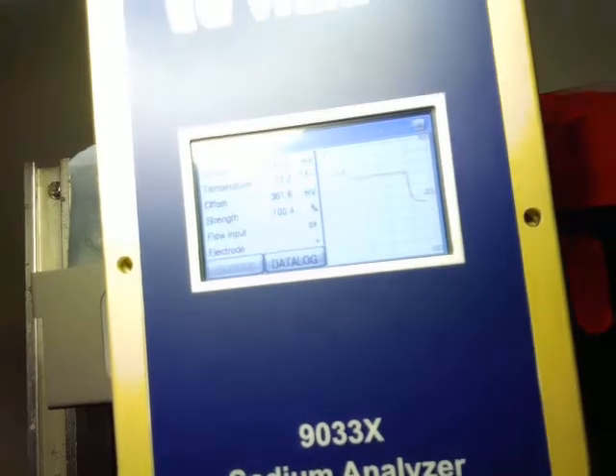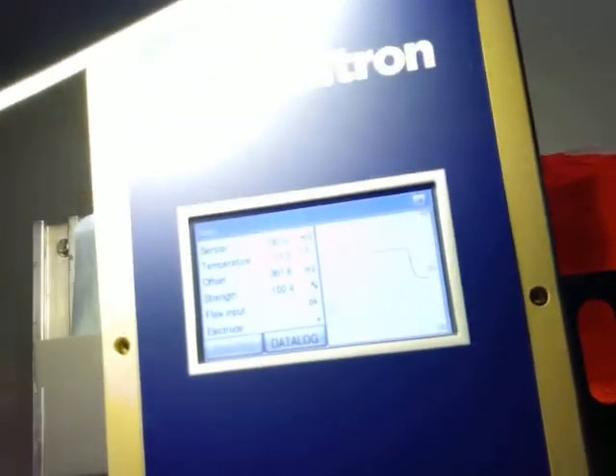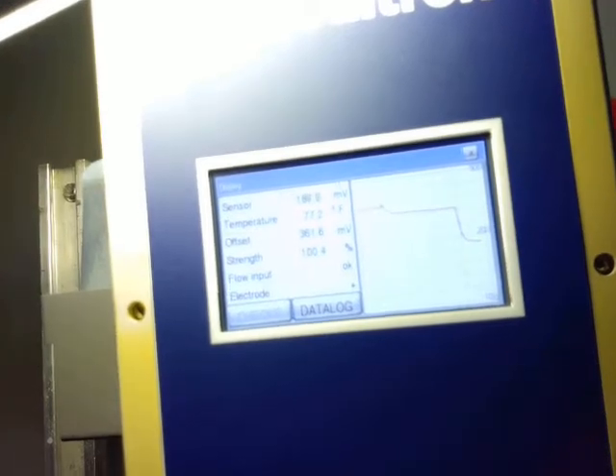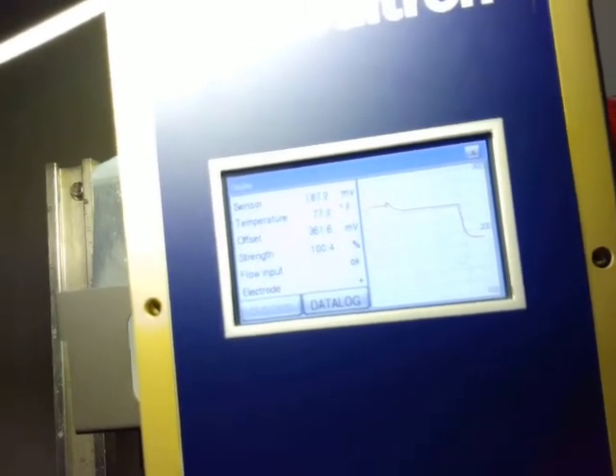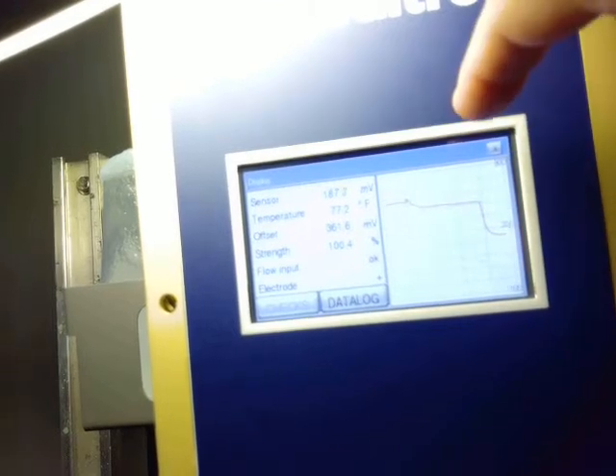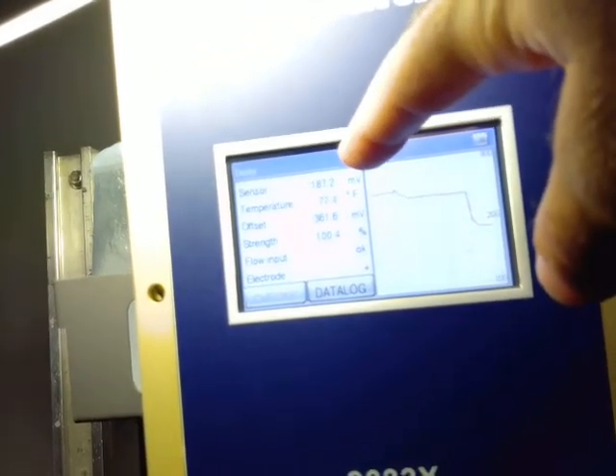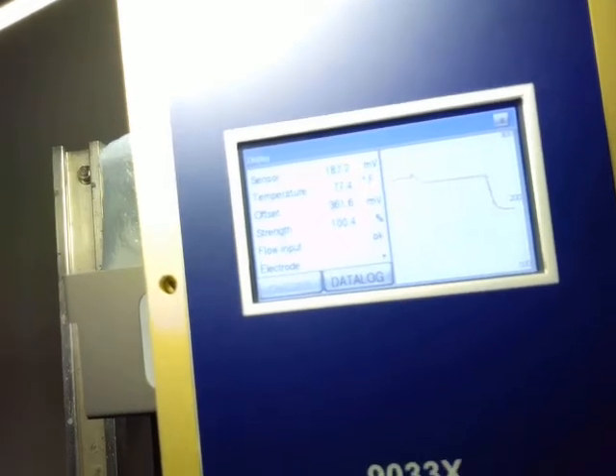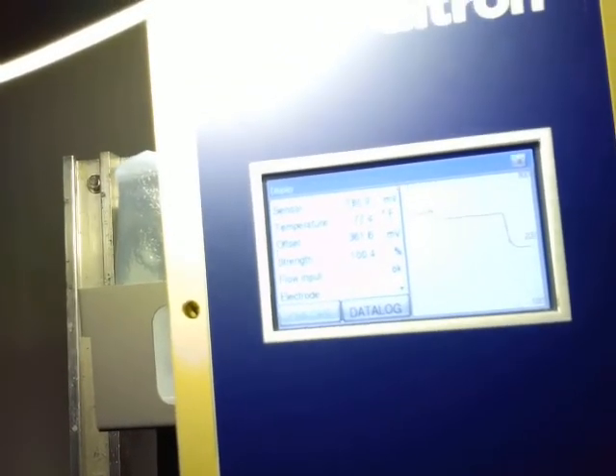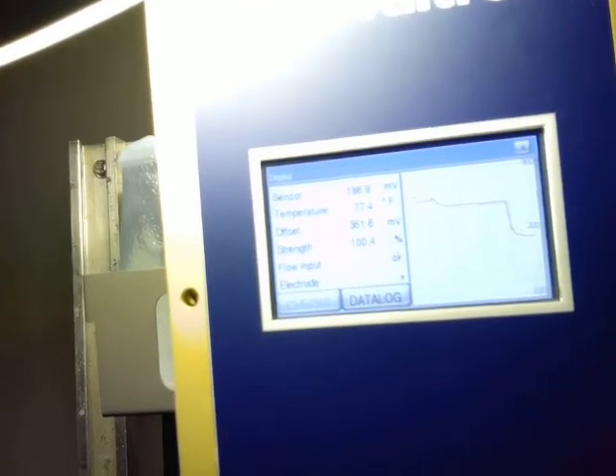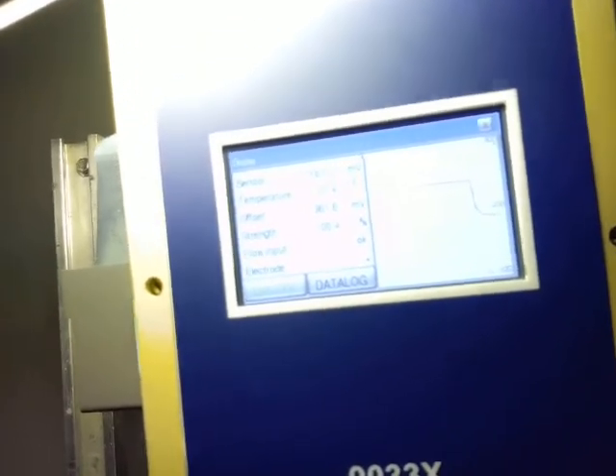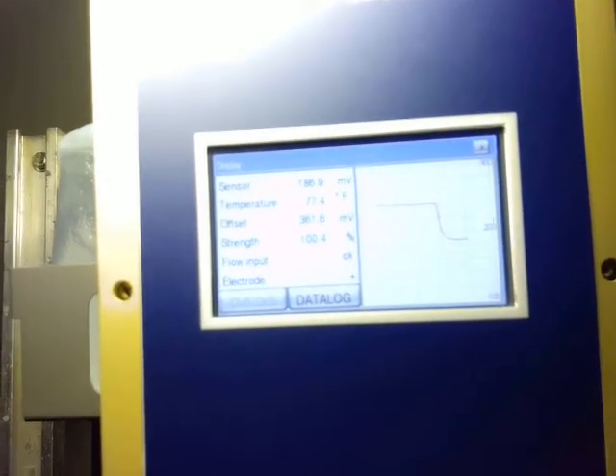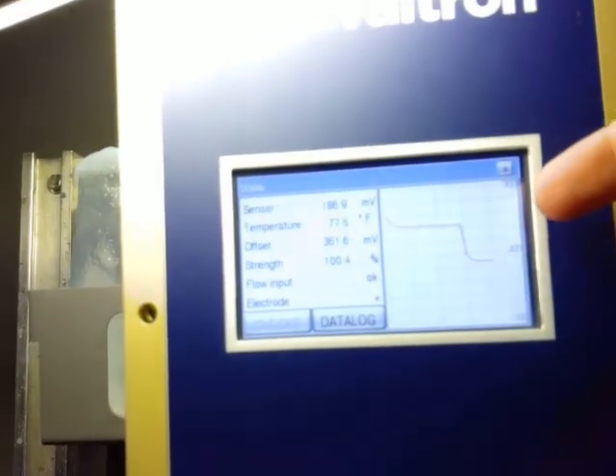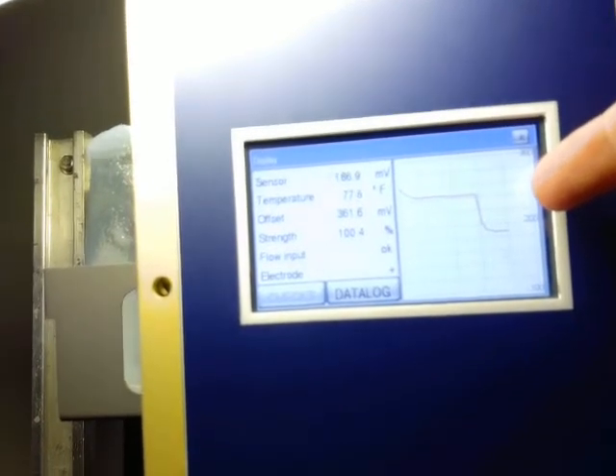There you go. That's kind of what I was hoping to see. All right, so we can start to see now this graph a little bit, which is just giving you a live reading and a plot of our sensor value, which is changing a little bit here. So that sensor value is just our live reading of what the electrodes are putting out. And it's not really too helpful to see, other than that, when we go for a calibration, we're looking for the difference between the two standards. So we're not necessarily looking for a certain number on that millivolts, but we're looking for this step change here. There we go, see it a little bit now.